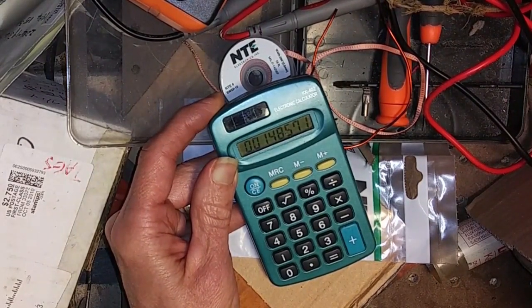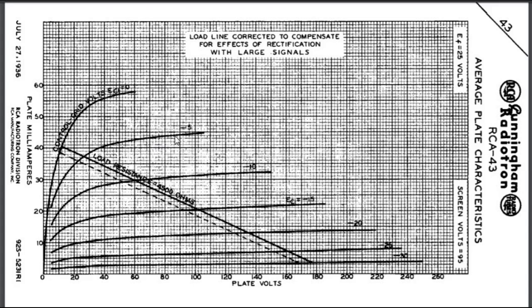15 milliamps. So if we look at the data sheet with about 90 volts on the plate, we should be getting a current of about 45 milliamps. In other words, we're only getting about a third of the expected current. So we might consider replacing that tube.